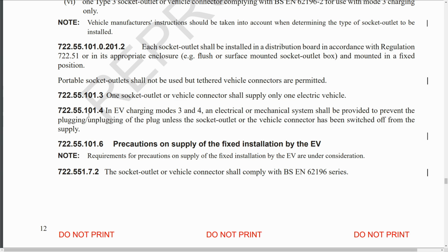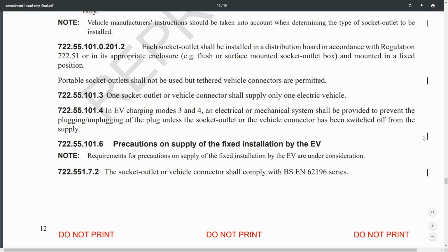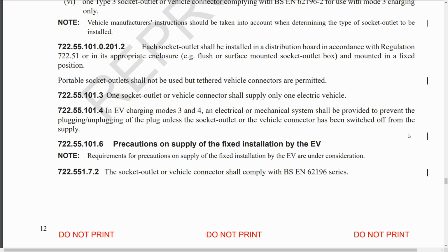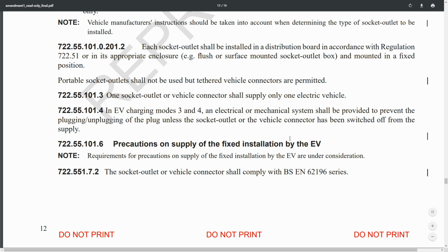Now the section here between 1014 and 1016, which of course was 1015, has been deleted for some reason. And why it's been deleted is not clear. What it used to say is that the lowest part of any socket outlet should be placed at a height of 0.5 to 1.5 metres from the ground. And now apparently you can put them anywhere you want. So you can put them on the floor, on the ceiling, or wherever else. But of course, in reality, it's going to be fixed at a sensible height. You don't really want it below 0.5 metre because it's going to get damaged and kicked in and whatever. And there's also the possibility if there's some flooding, it could be underwater. And obviously, fitting it greater than 1.5 metres from the ground means that no one will be able to reach it. So again, not particularly useful. Not clear why that's been removed, but that's what it said. But really, the concept of it is not changed.